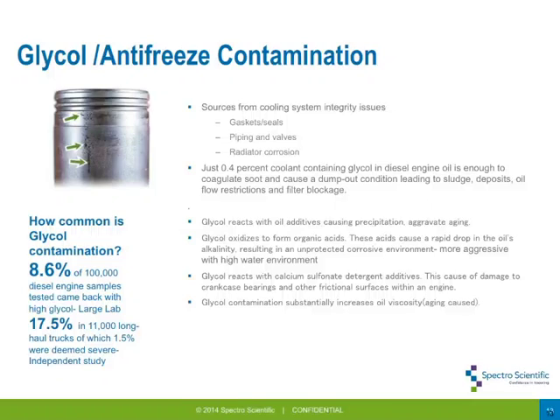In recent years, many OEMs and operators with large engine fleets have started to beef up their capability for coolant analysis, because when coolants start to degrade — especially with new technologies — it can affect the entire engine performance. From our side, we're worried about what happens when coolant gets into the oil. Studies show that anywhere from 8% to 17% of engines, depending on the study, have had coolant contamination. When you do have that, you need to address it quickly — when you have coolant in there, you may also have a water problem developing simultaneously.